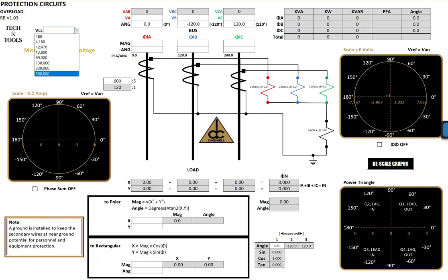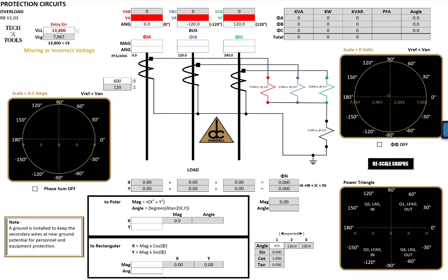way up here to 500, 1,000 volts. There can be higher voltages in this country. This is what we see a lot of. Let's start with a distribution voltage, and you'll notice here that the line to ground is found by taking the voltage line to line and dividing it by the square root of 3. So for any one of these voltages up here, I'll just pick one about 480.